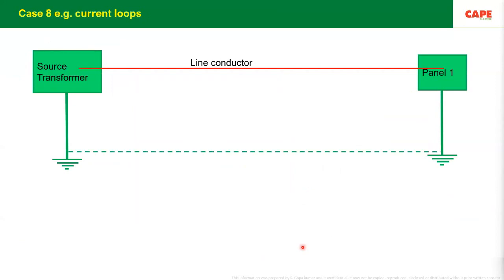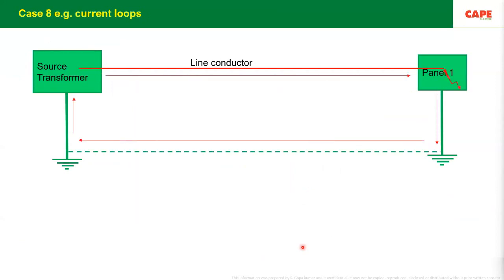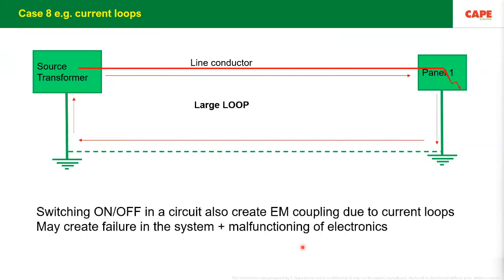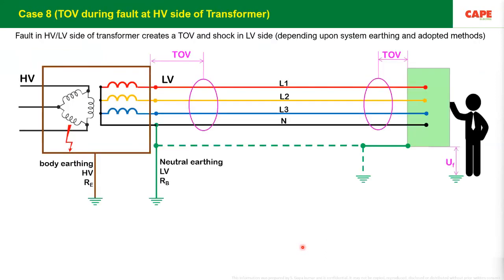Case number 8, current loop. Every electrical wiring shall be made in such a way that the circulating current takes the shortest path back to the source. If we take a longer path, it may create problems such as electromagnetic interference, and it can cause your electronics to malfunction. Also, the same case number 8 covers temporary overvoltage, meaning a fault on a transformer. I'm showing you a transformer here on the left side. There is a fault on the transformer on the HT side. Whenever there is a fault on the HT side of a transformer, equipment in your building can burn.